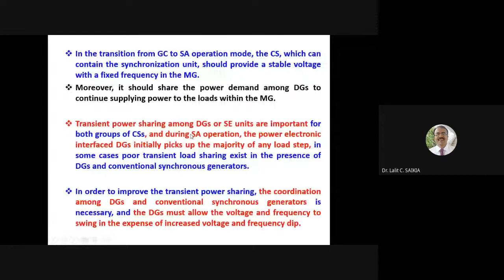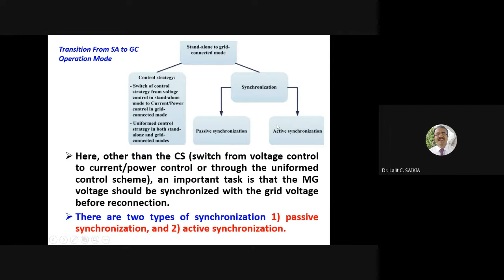Here, other than the control strategy, switch from voltage control to power control or through uniform control, an important task is that the microgrid voltage should be synchronized with the grid voltage before reconnection. This should be synchronized. There are two types of synchronization. One is called passive synchronization and the other is called active synchronization. In passive synchronization, the microgrid voltage and main grid voltage are monitored, and the two grids are connected when they have the same phase angle.